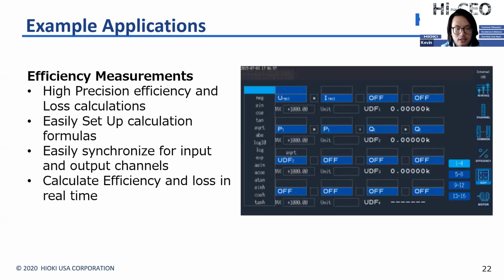In particular, we were able to simultaneously measure inverter input and output and the motor output. This helps us evaluate the overall system efficiency and loss in an accurate and reproducible manner. We should also keep in mind that to improve the accuracy of our calculations, all the measurements should be taken simultaneously, because if we don't synchronize everything perfectly, this will affect our results.